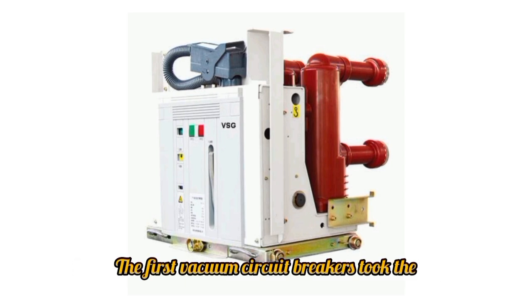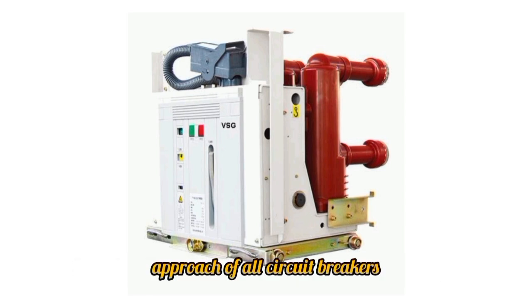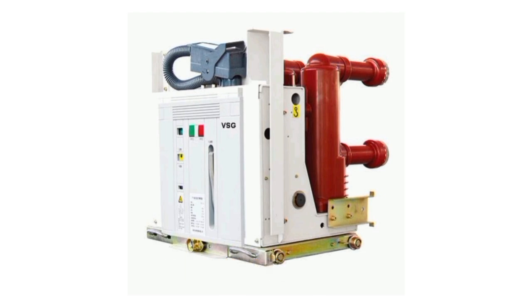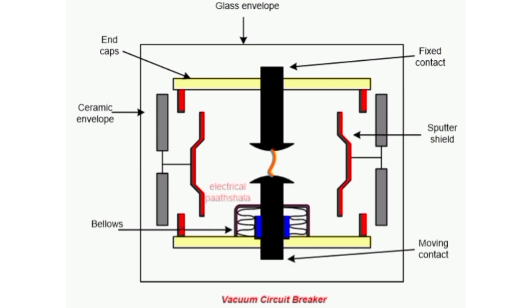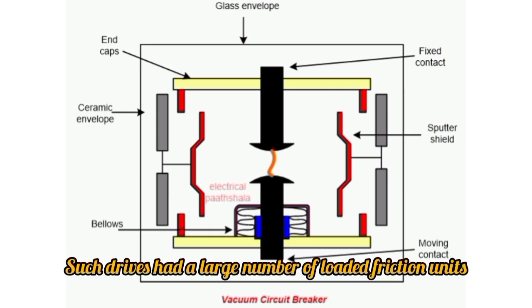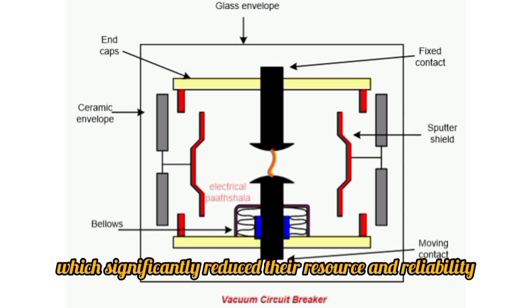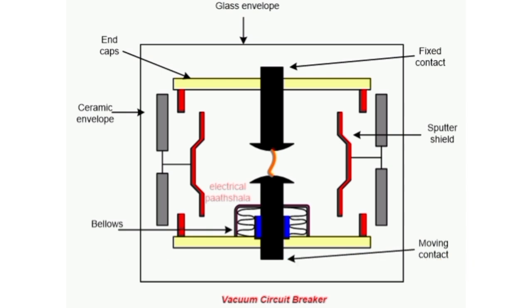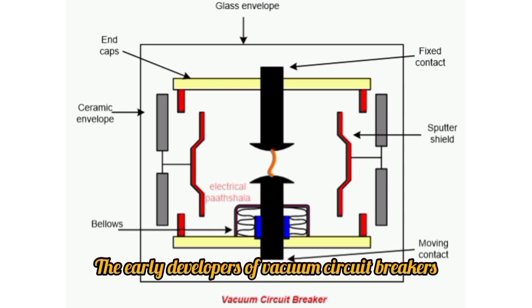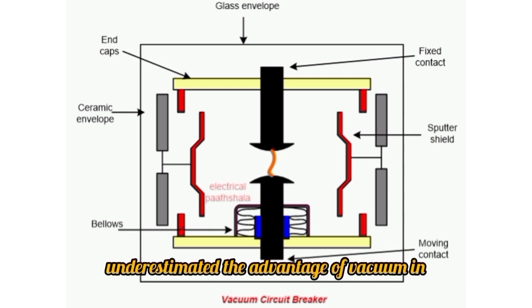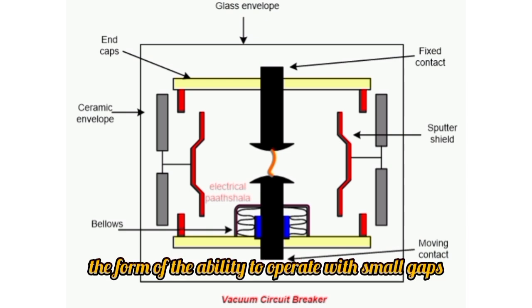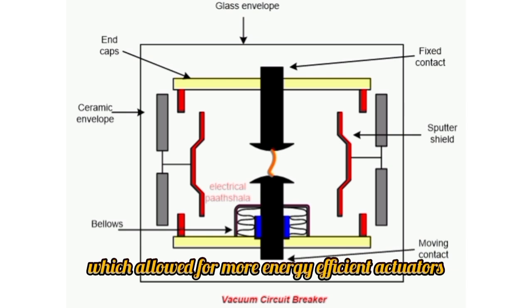The first vacuum circuit breakers took the approach of all circuit breakers and used bulky spring motor actuators to open contacts. Such drives had a large number of loaded friction units, which significantly reduced their resource and reliability. The early developers of vacuum circuit breakers underestimated the advantage of vacuum in the form of the ability to operate with small gaps, which allowed for more energy-efficient actuators.